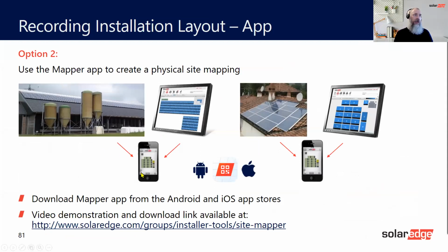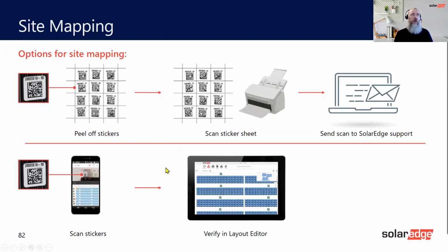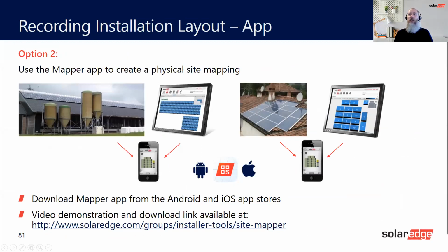The Mapper app is free, as I said. The beauty of this is it allows you to scan the optimizers before doing the inverter. What we recommend is that you create the site in Designer and export that site into the monitoring. When you've exported it into the monitoring, you then put that address into your mapping app, and as you scan the optimizers, that will automatically update onto the physical layout.